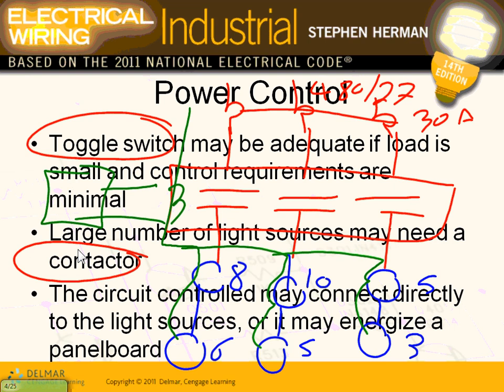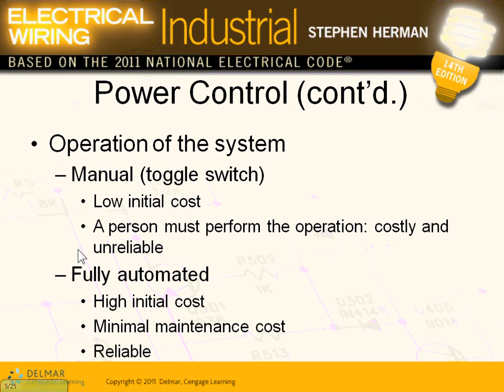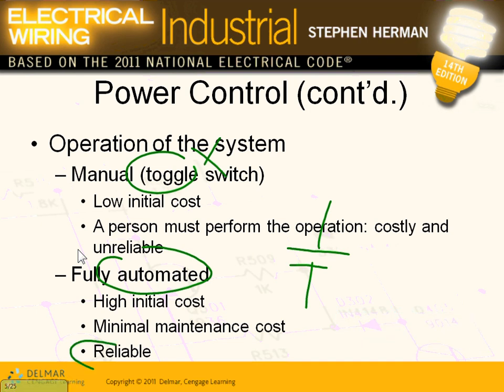So your major control options: you have your timer, you can have a magnetic contactor, you can have a snap switch. We talked about the toggle switch — typically not used well. When we say automated, you're talking about a magnetic contactor, a timer, or some type of relay. It gives you better control — you can interface it with technology. There's no way to turn a wall switch from your computer, but with a lighting contactor you can interface it with any control system you want.